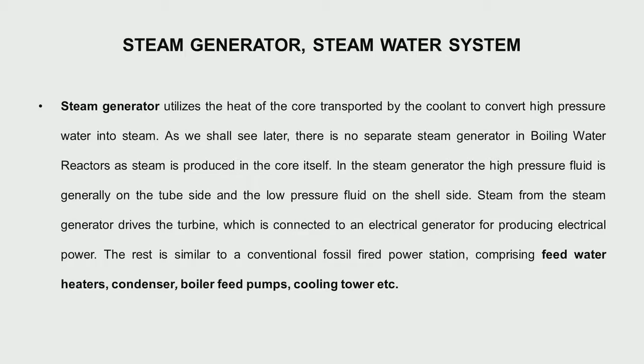We will just have a look at which are the components. See here, this is the steam generator. The steam which is produced goes here, it is a high pressure turbine, it does work in the turbine, but as it does work in the turbine, the quality of the steam comes down and at some stage it becomes wet. Now you see the turbines use very fine thin blades. So there is a limit on the amount of wetness that they can withstand, because any water particles will cause erosion of the blades. So normally it is about 10 to 12% wetness, more than that it cannot be there.